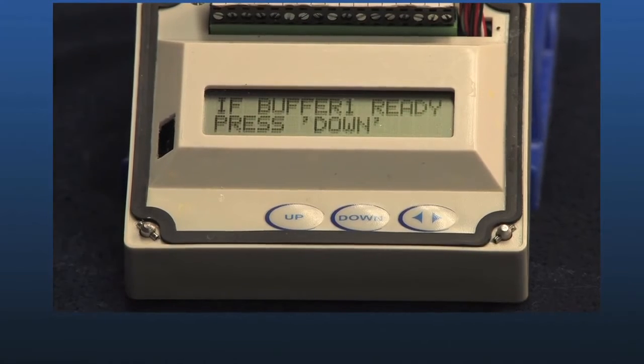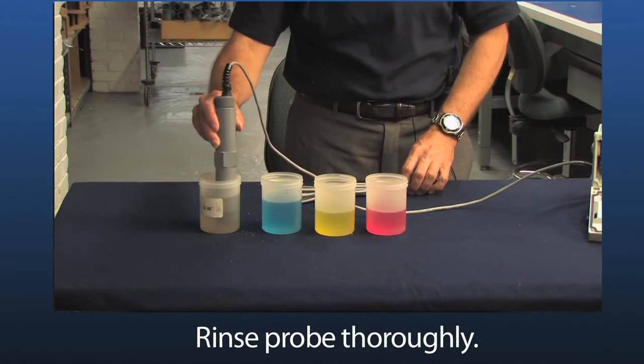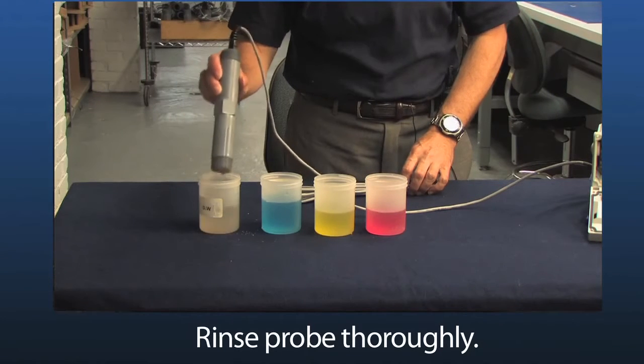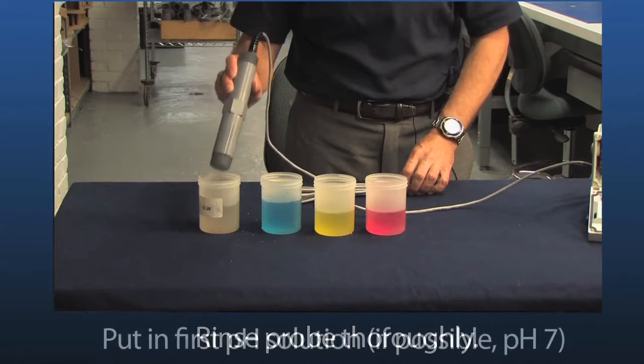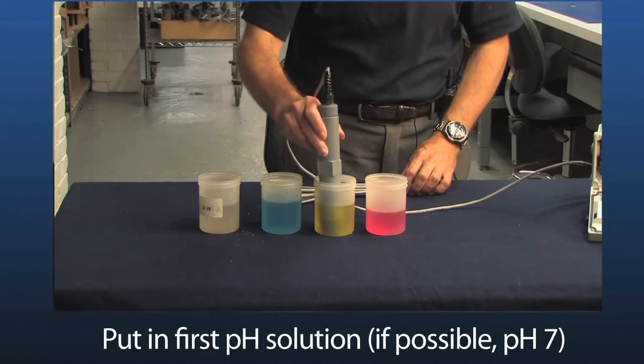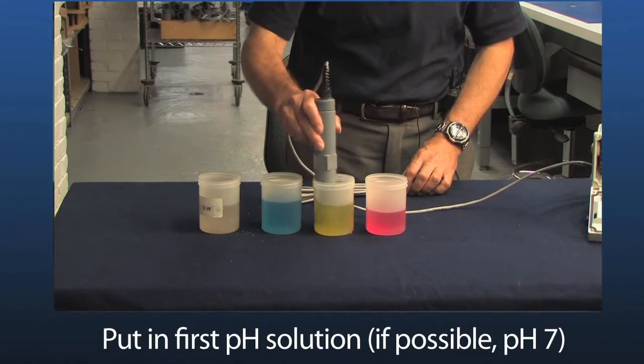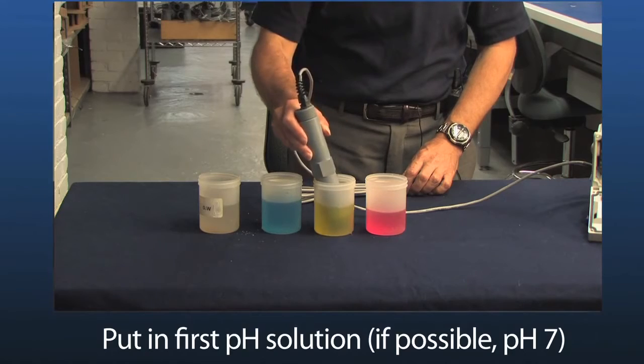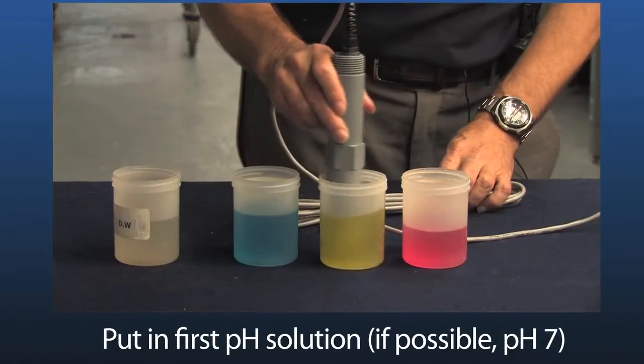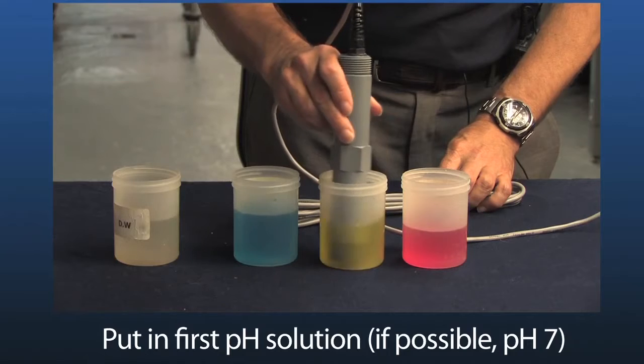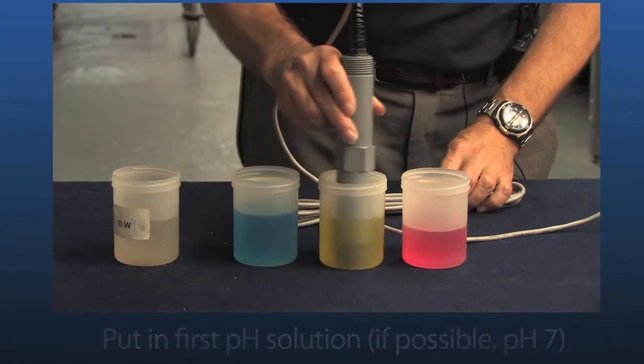The first thing I'm going to do before I put my probe in buffer 1 is to make sure I rinse it very thoroughly. And if I'm using a pH 7 buffer as one of my two calibration solutions, I'll make sure that I put my probe in pH 7 first. So I'll stick it in the pH 7 calibration solution. I'll swirl it around to make sure I get really good contact and flow over the process electrode.